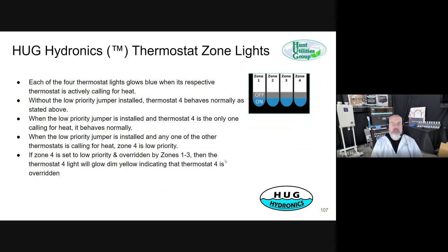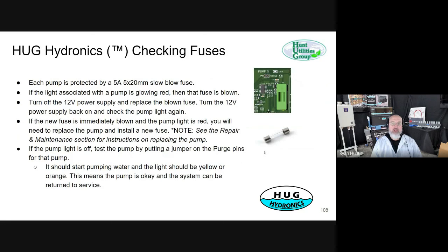The thermostat zone lights are pretty self-explanatory. When a thermostat comes on, its corresponding light turns on. As I mentioned, zone 4 can be low priority, and if it's asking for heat and it's being overridden, it turns yellow. Checking the fuses: they're easy to get. We send a spare one. You pop the green cover off. We've never had one fail in the field. Never blown a fuse because of the smart design of the pumps.